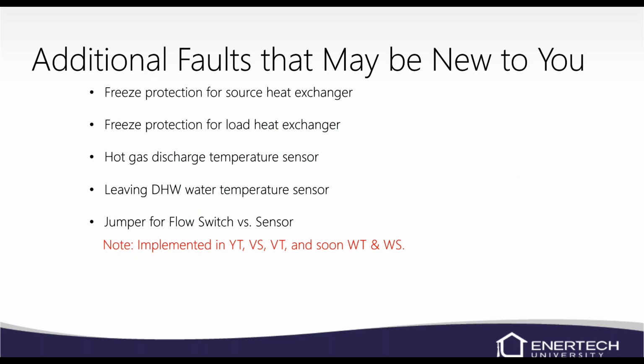So when we went to the newer board, we added freeze protection for the source heat exchanger, freeze protection for the load heat exchanger, a hot gas discharge temperature sensor, and a leaving domestic hot water temperature sensor. We've also added a jumper or a dip switch, depending on the revision of that board, so you can choose whether you're going to monitor a flow switch or a sensor. And we'll get into what that really means in just a minute.